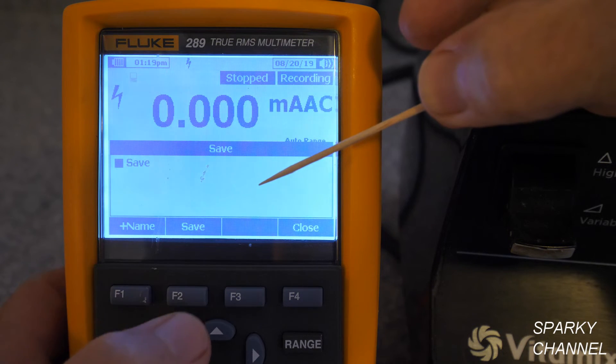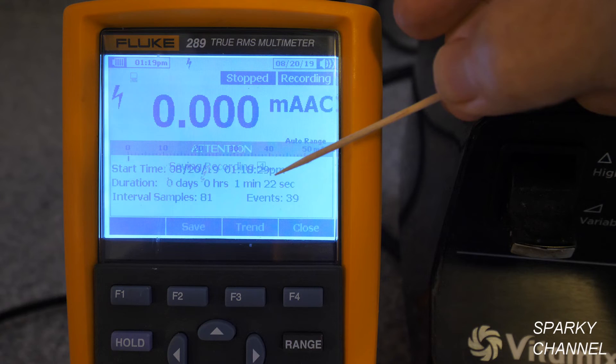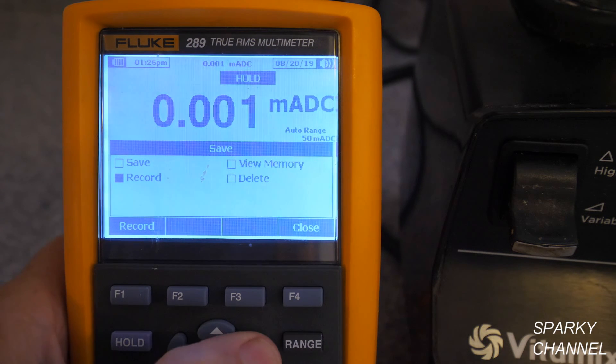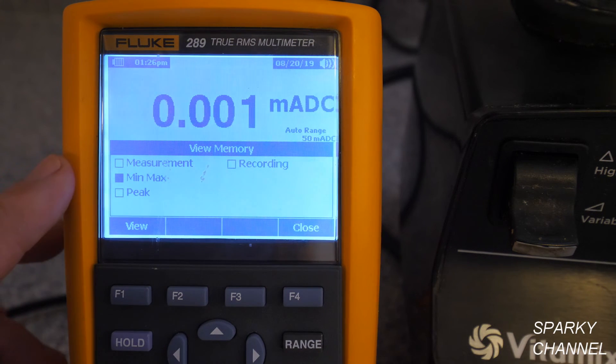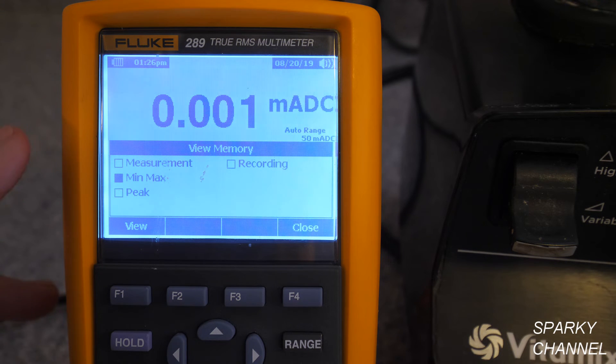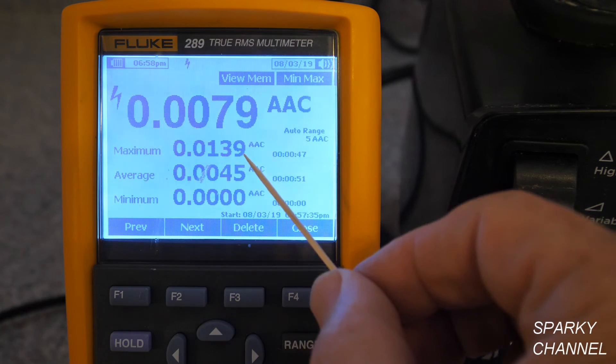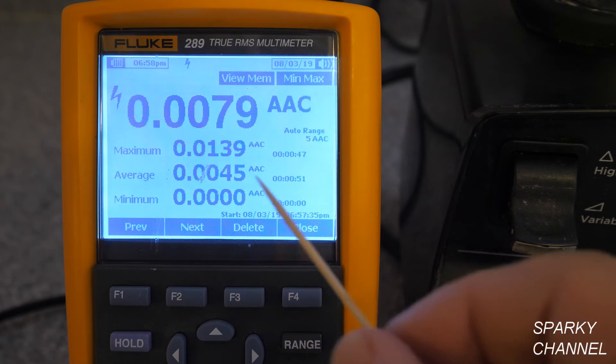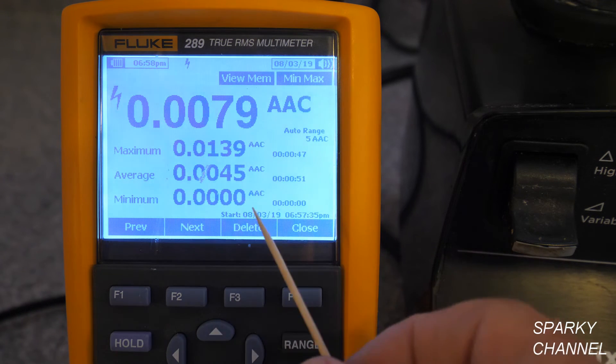I'm going to say save. Name. We'll call this recording 4. And I save it. Now I'm going to press save. And we're going to get out of record. We're going to go over here to view memory right here. There we go. And I'm going to say view. Minimum, maximum. Because remember, I wanted to see exactly how high that amperage got. It looks like it got a little over 12. Well, actually, the maximum was 13.9 amps AC. That's because you have to multiply this reading by 1,000. Because we're using the AC current clamp, the I-400 AC current clamp. So the average would be 4.5 amps AC. And the minimum was zero. So we'll close that.